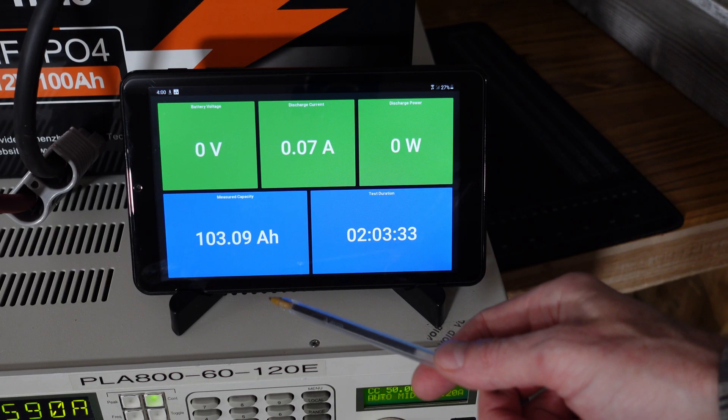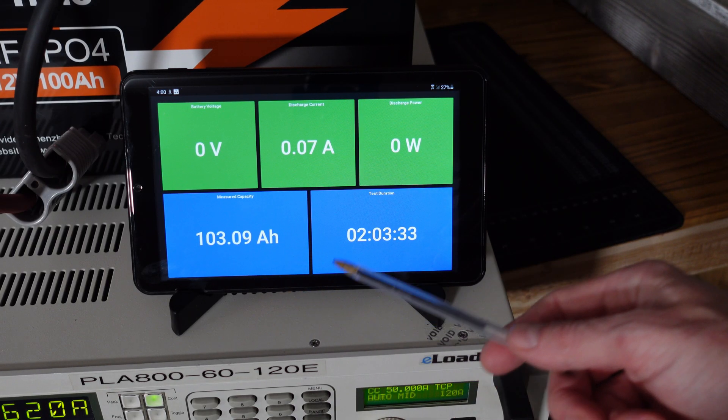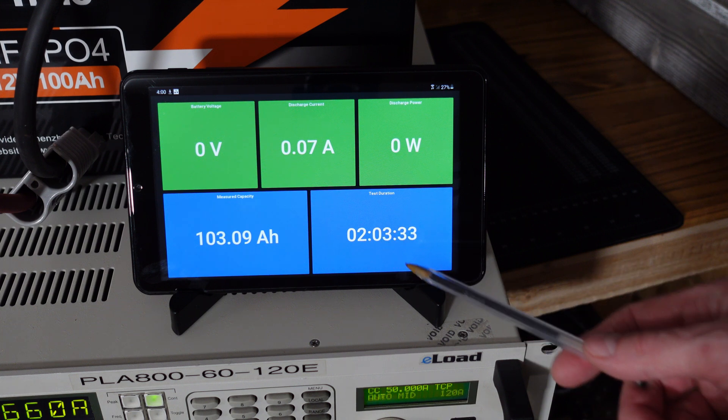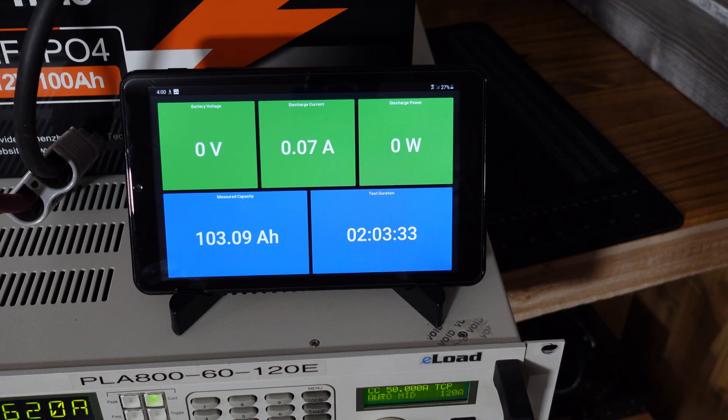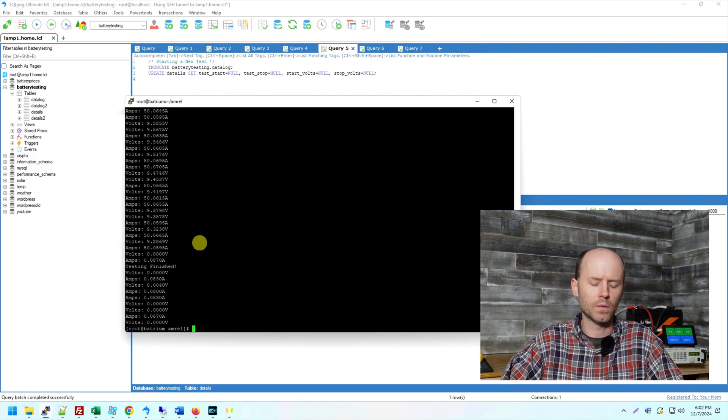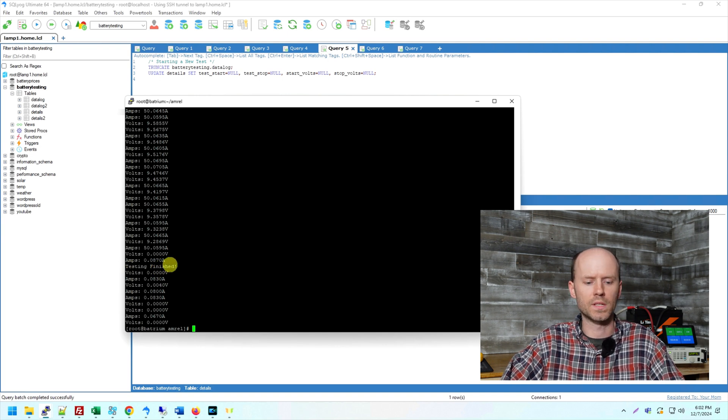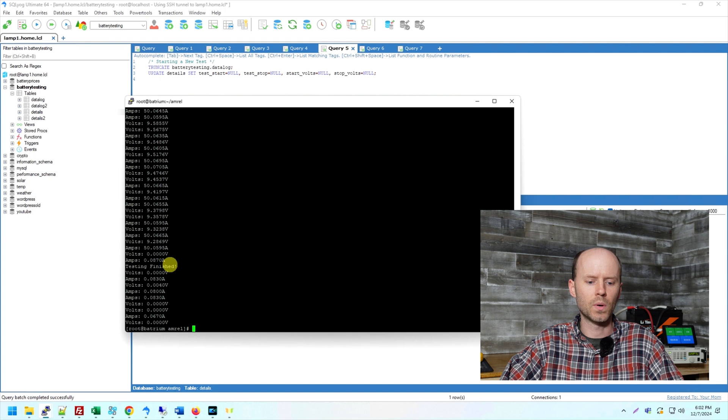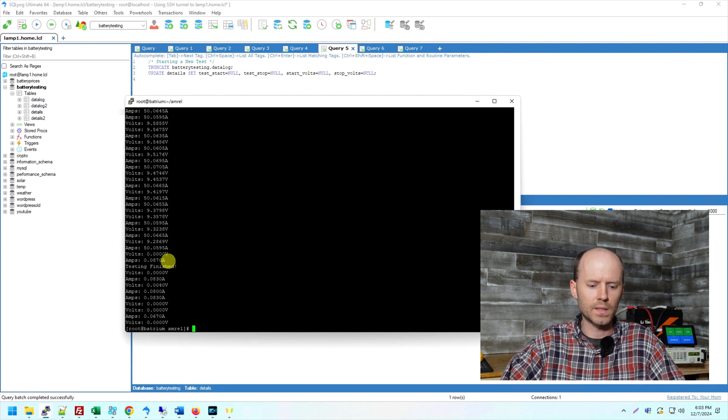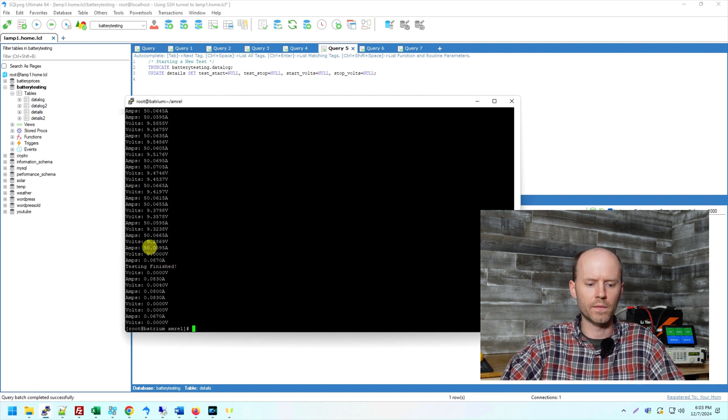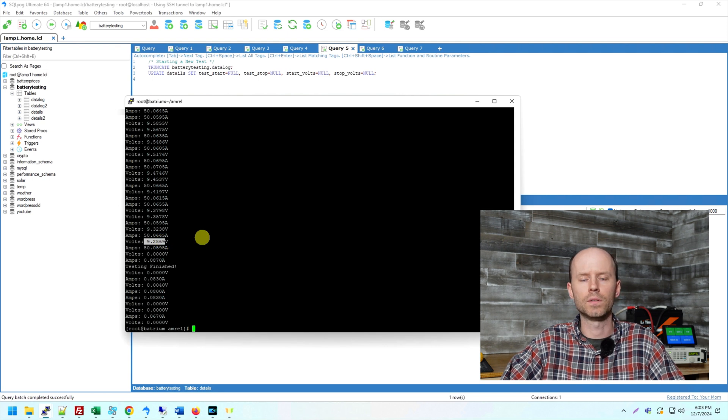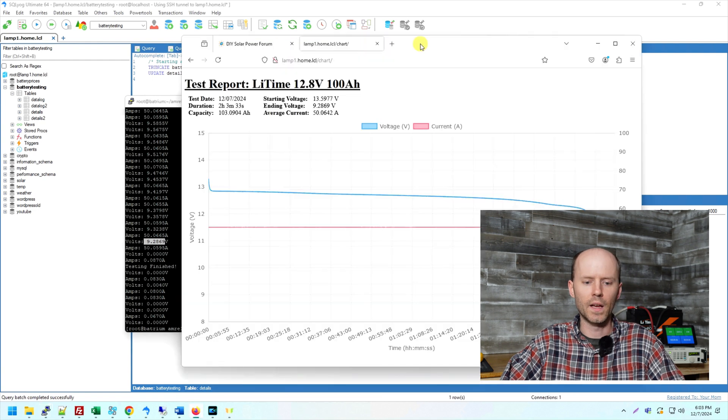The test has concluded. We came in at 103 amp hours and it took two hours, three minutes and 33 seconds. And taking a look at our computer again here, we can see where it detected the test has finished. Once the current dropped to 0.08 or otherwise shut off, that's the point at which the BMS disconnected. And we can see the voltage immediately before that event occurred was 9.2869 volts. We then continued to sample data for five more seconds and then exited.